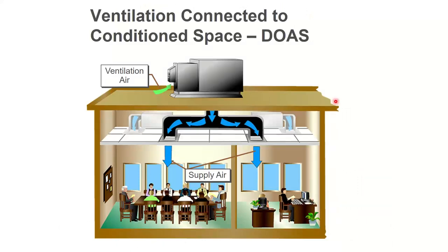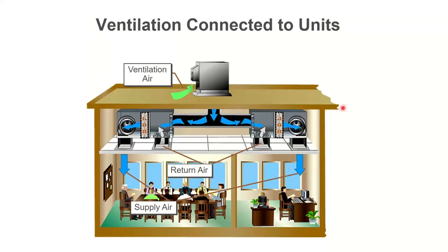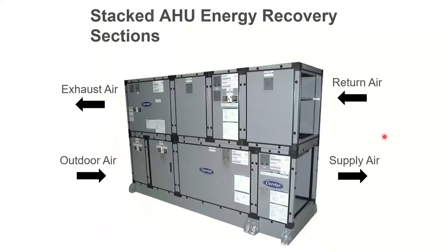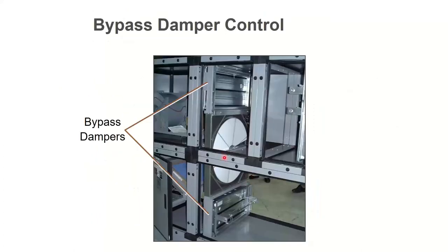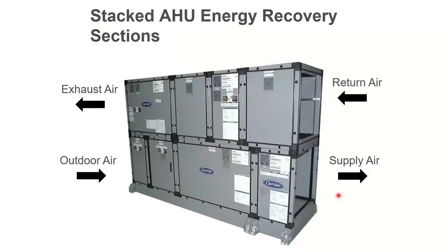The way you connect these to the air handling system, I'm way behind, I've got to power through here. You can either directly duct it into the space. That's a problem because you're dumping semi-conditioned air on people instead of fully conditioned air. You instead could duct it into the fan coils. These could be ductless mini splits, they could be fan coils, they could be air handlers. It could be a one-to-one relationship, it could be a one-to-five relationship. You duct it into the air handler, mix it with the return, finish heating or cooling it, and then send it into the space. You can have it inside the main air handler, like on a VAV system or something like that. You can have a wheel or a core inside there doing its thing, in which case these two airstreams have to crisscross.